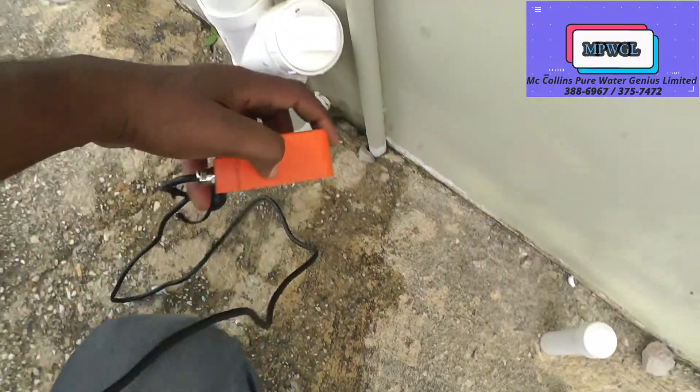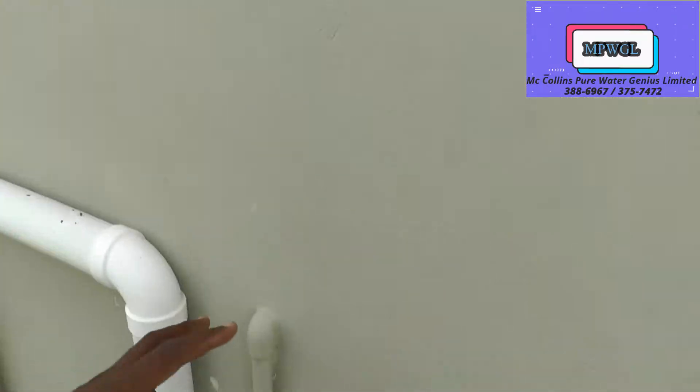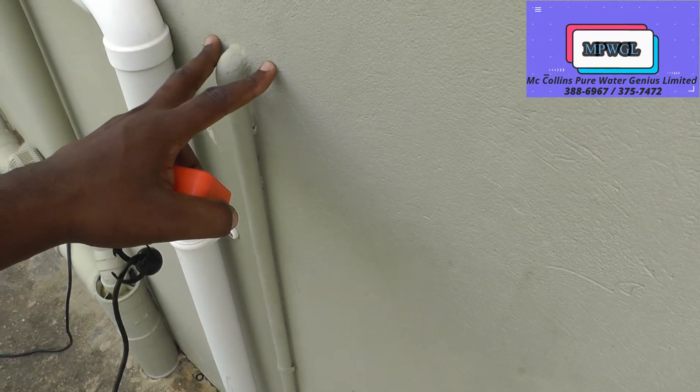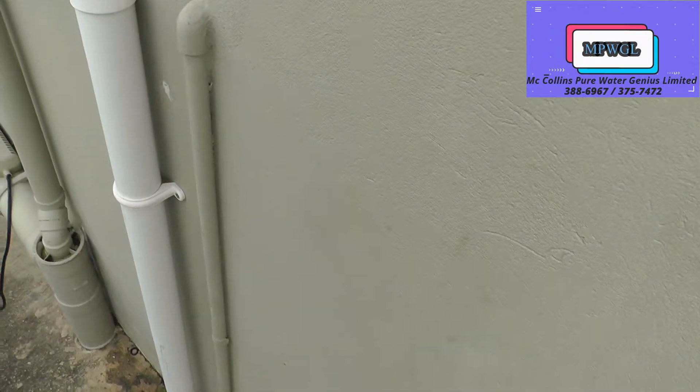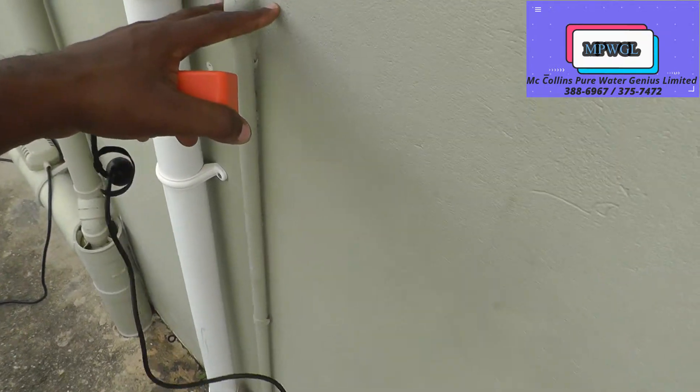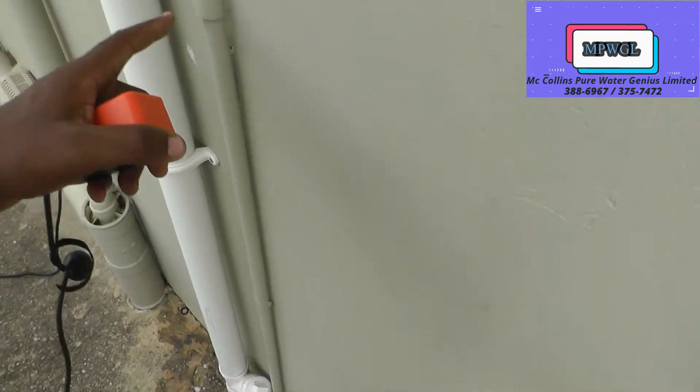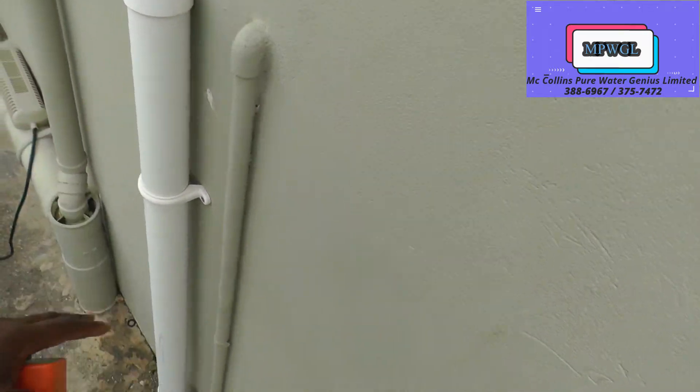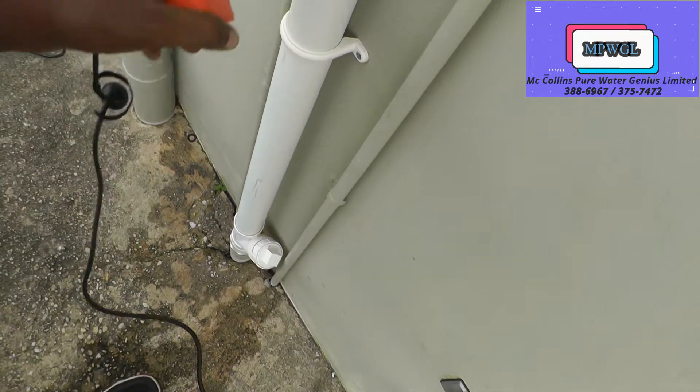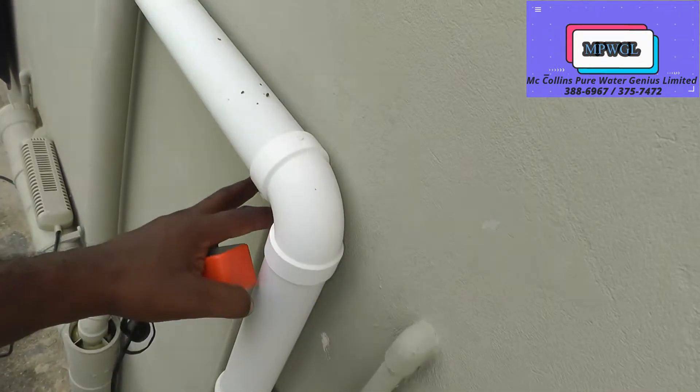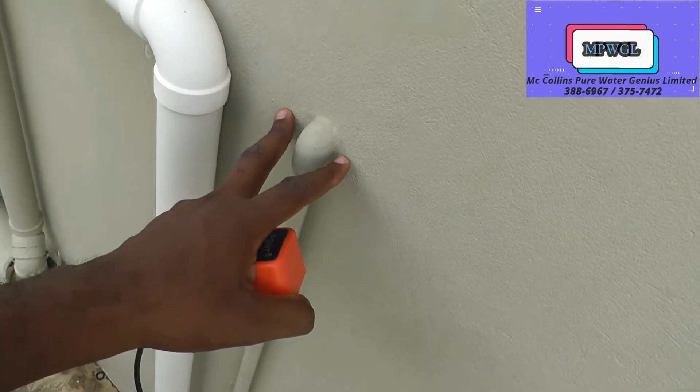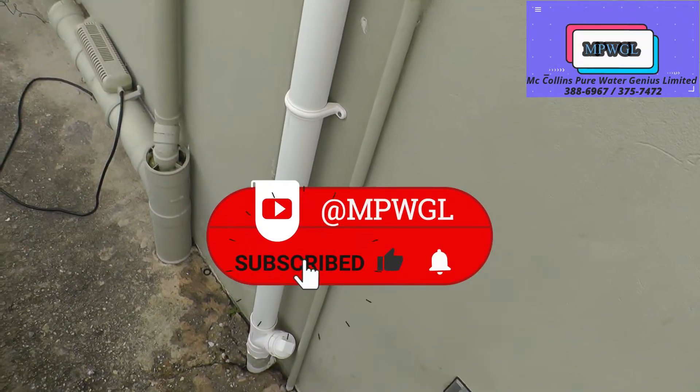I know for sure there's no leak here. So right here, which is the mixer cold water going into the mixer, it has some leaking line inside here. So they will just need to burst up this area here, find the leak and patch it. They would not need to burst up the flooring or interfere with the hot water line. So it's just the cold water line. All right, showing with MPWGL. See you guys next time.